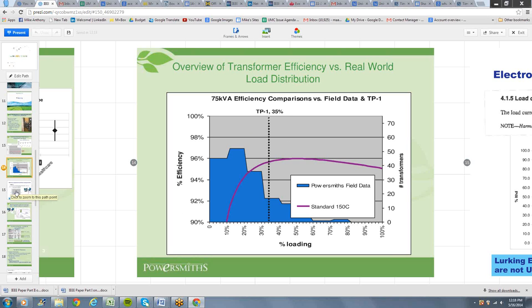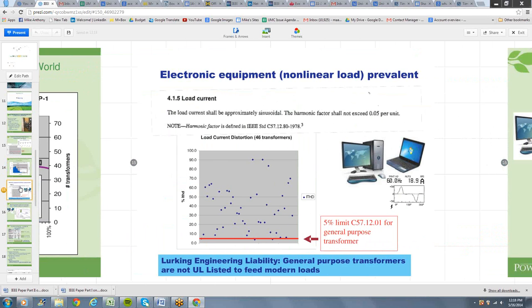On the next slide, we're going to look a little more at what that load is made up of. And as you can see, we just think about low voltage, so 120 volt, all these receptacles. What are we plugging in? Well, we're not plugging in baseboard heaters and incandescent lights. We're plugging in electronics, right? And when you look at the load profile of a piece of electronics, this is a 120 volt switch mode power supply, which is very common. As you can see, there are pulses of current instead of a nice sine wave. And as a function of that, it introduces quite a lot of extra heat into a transformer, and as a function of that, reduces its effective capacity.